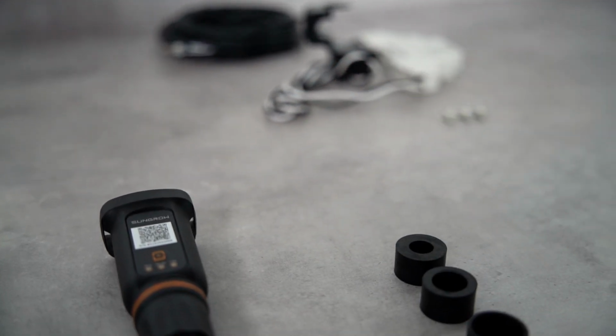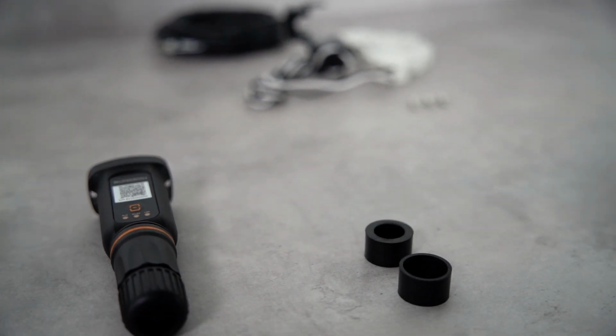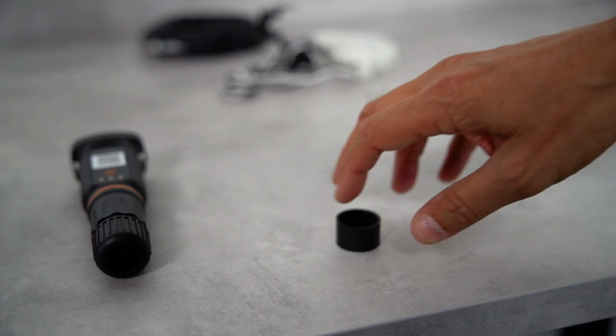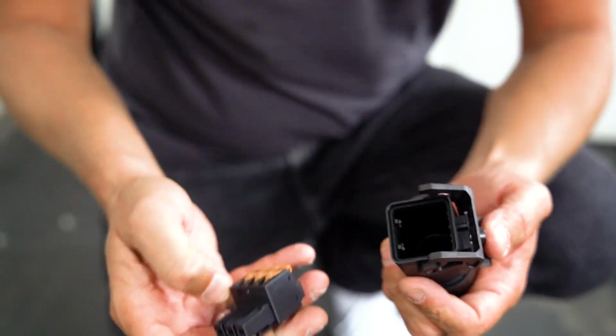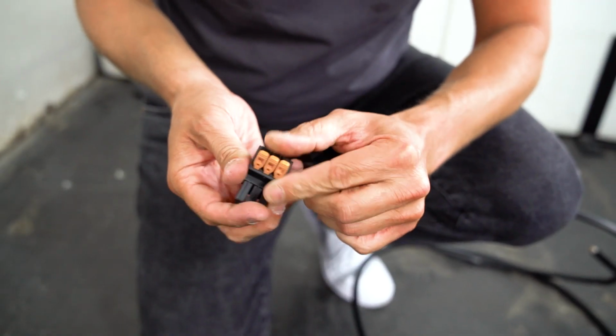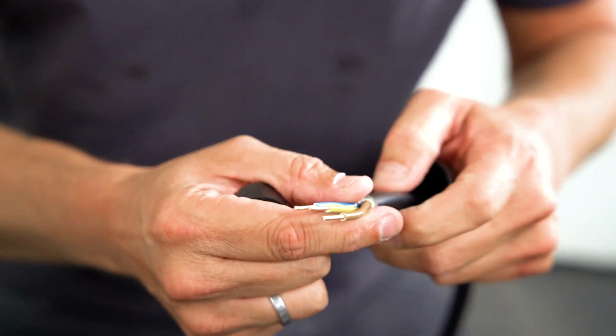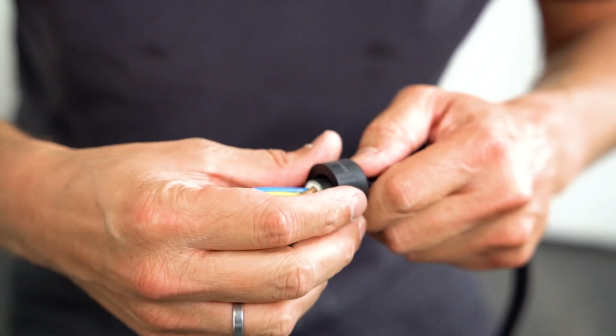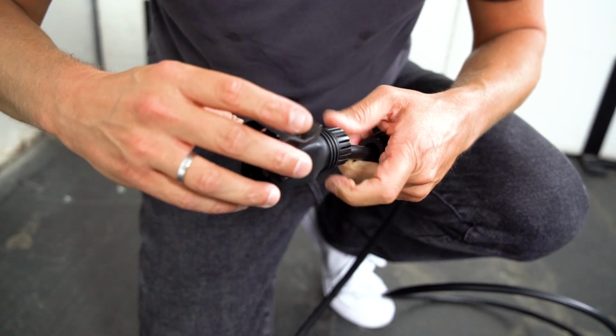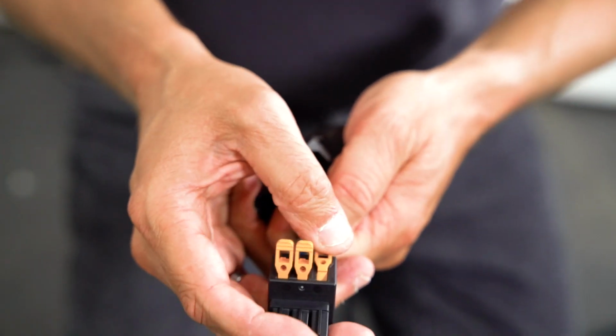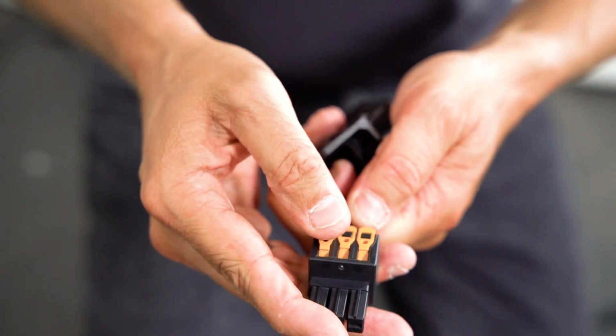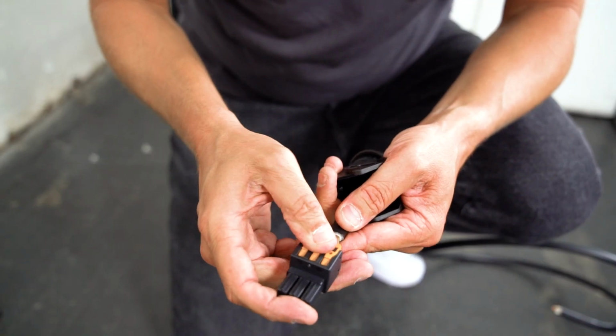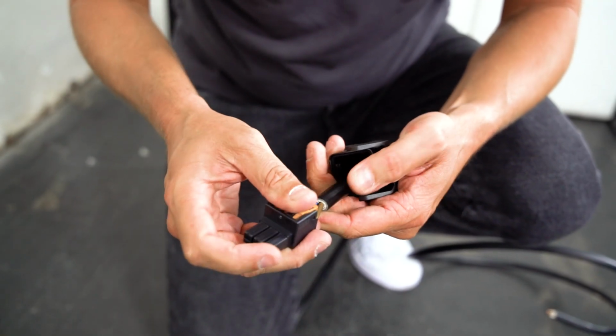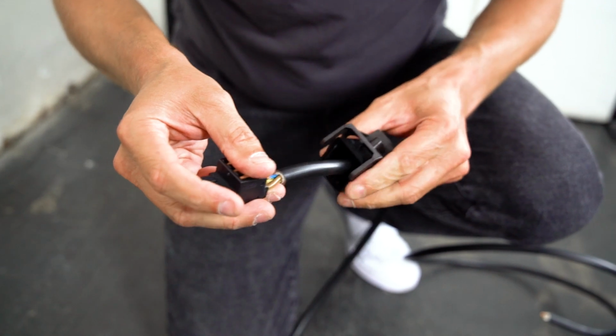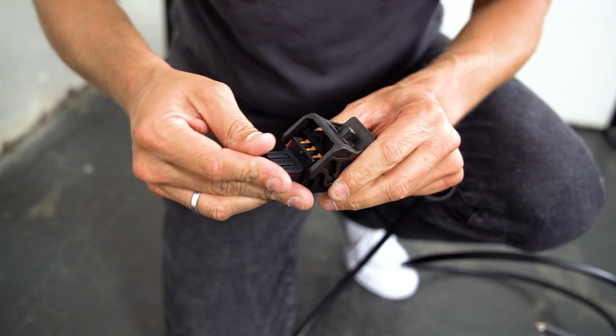In the next step, we will install the backup plug. Remove approximately 4 to 5 cm of the cable sheath of the cable. Then strip approximately 12 to 15 mm of the inner cables. Pull the cables through the individual components and fix them with 3 simple clicks, completely screw-free. Make sure that all cables are fixed to the respective terminals. When all cables are in place, push the terminal strip into the housing of the plug.